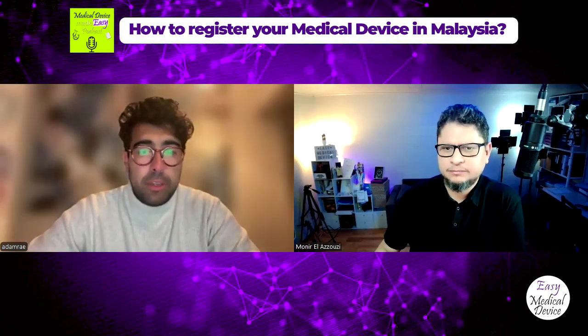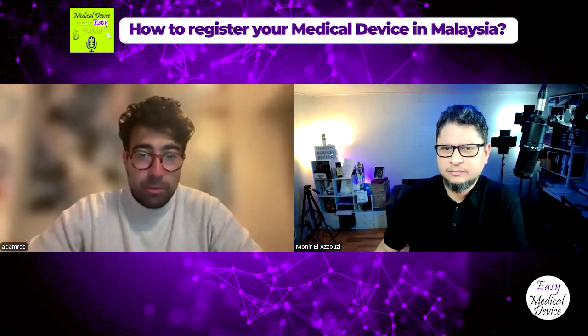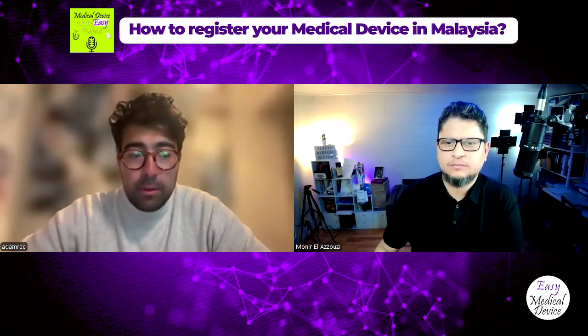Yeah, so it would be your authorized representative. They will become the face to the authorities. So it's really important you have a good one. Really important you trust them, because there's going to be a lot of IP handled here. They will have to hold your technical documentation. They will know about any complaints that occur. The authority will go to any changes that happen to your device. They will know about it because you're going to have to make any updates to the conformity assessment body.